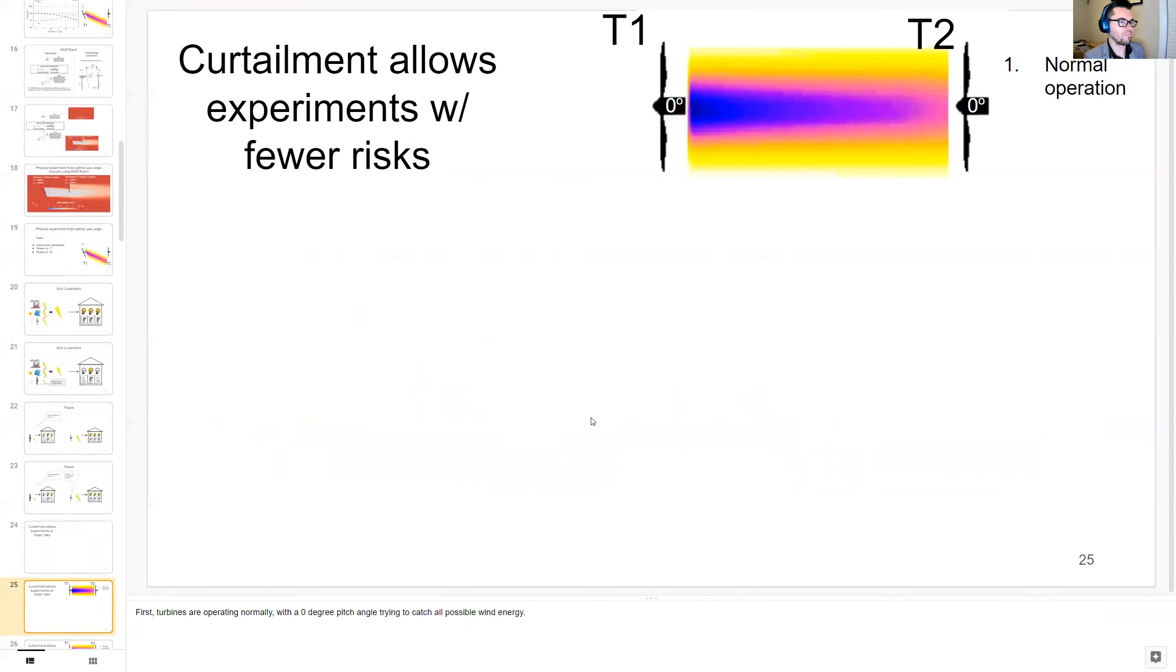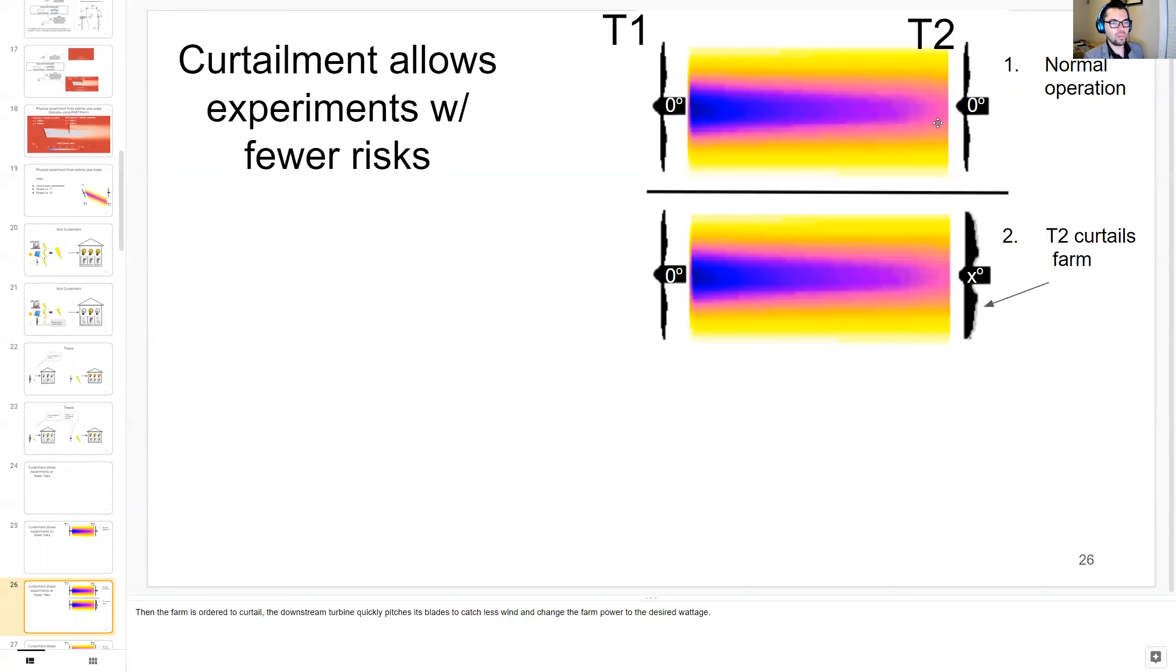So what do these experiments look like and how do they decrease the risks that I showed earlier? Basically the wind farm starts out with normal operation where zero degree pitch is being used, it's region 2 wind speeds, and then an order comes in to curtail the second turbine. It starts pitching its blades, decreasing the amount of wind it captures, and therefore decreases farm power to the desired wattage. Then lastly, the upstream turbine explores yaw angles while the downstream turbine continues varying its pitch to keep farm power at the desired wattage.